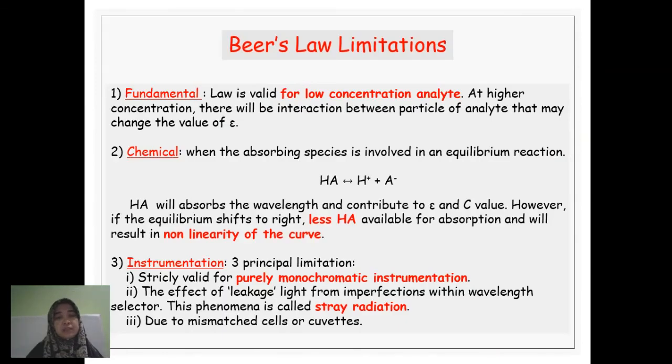Therefore, there are a few limitations to Beer's law. First of all, based on the fundamentals, the law is only valid for low concentration of analyte. At higher concentration, there will be interaction between particles of the analyte that may change the absorptivity. Therefore, the line will not be straight anymore.